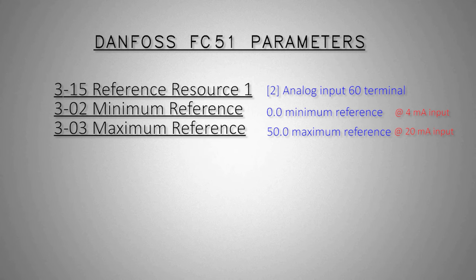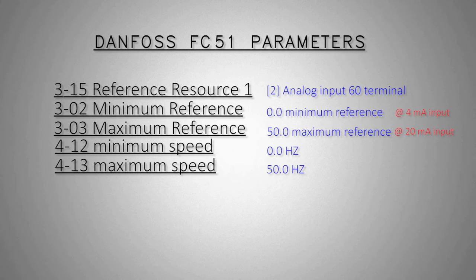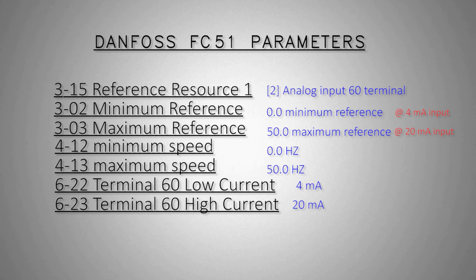Just a side note here: the speed of the motor will not exceed the speed entered in parameter 4-14, which is the maximum speed limit. If we want to run at higher speeds, we have to increase the speed limit in parameter 4-14. Finally, we have to set the minimum and maximum range of the analog input current signal for terminal 60. By default the minimum signal is set to 0 mA — we can change it to 4 mA. The high limit is set to 20 mA, and it is good to go.